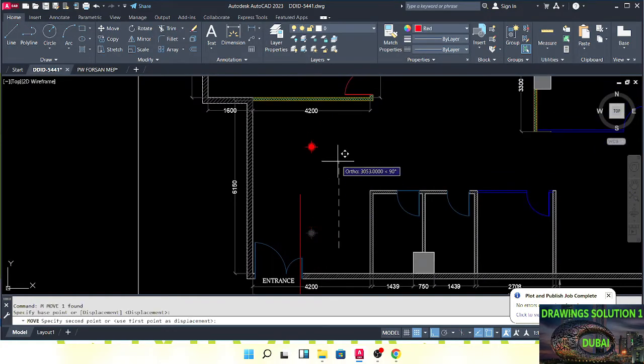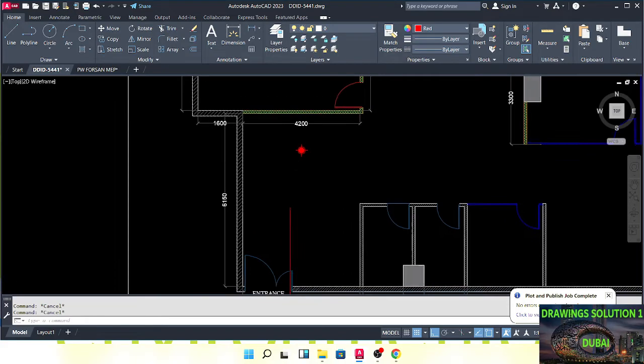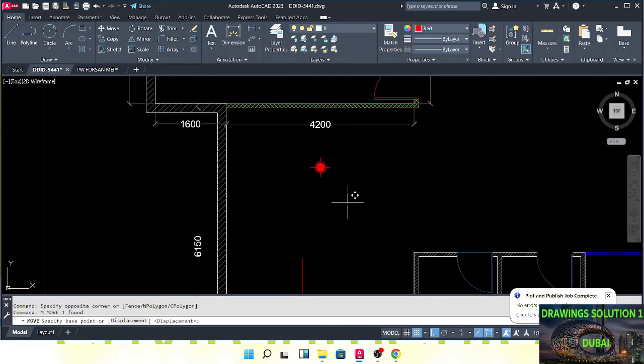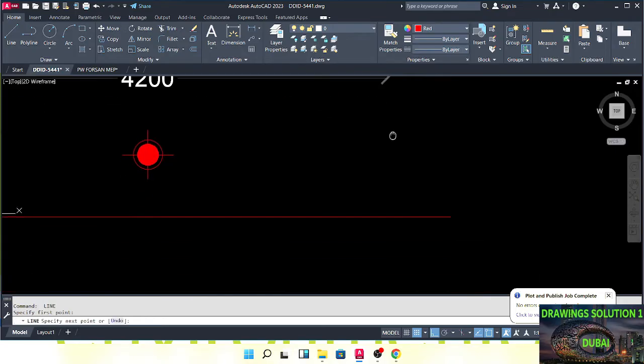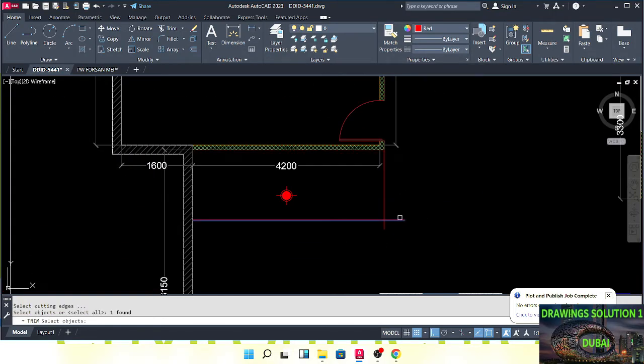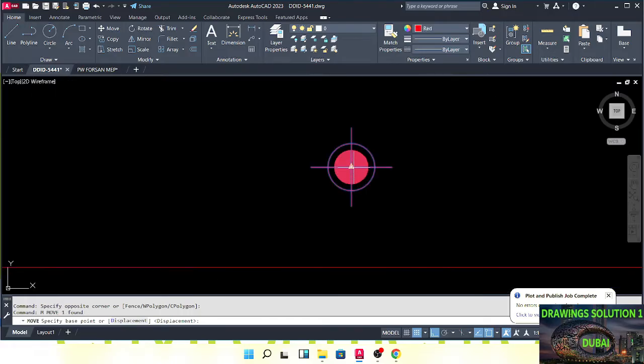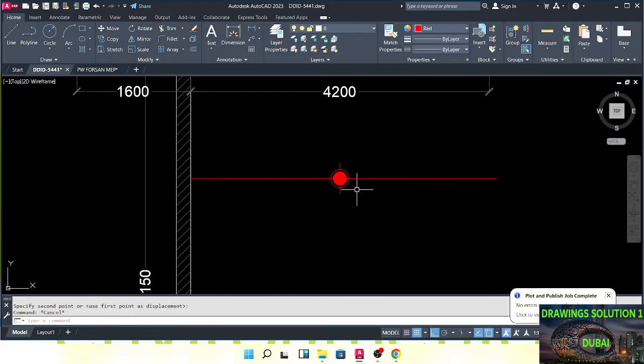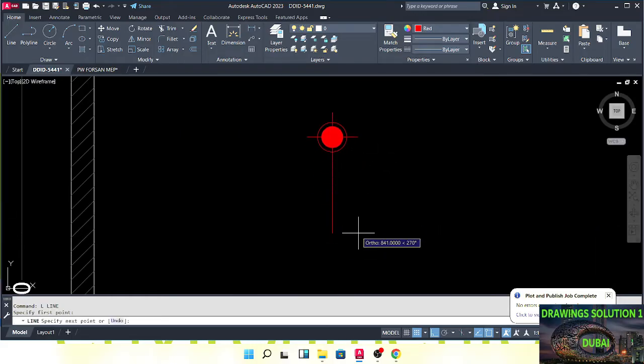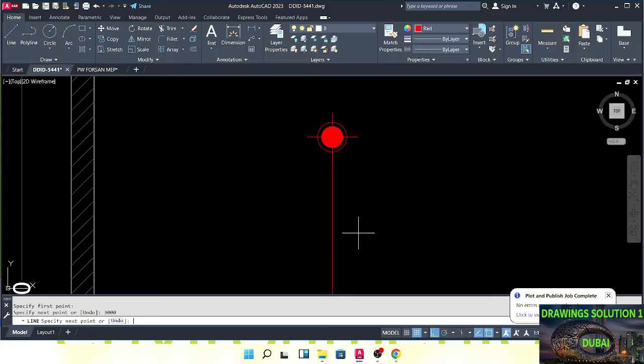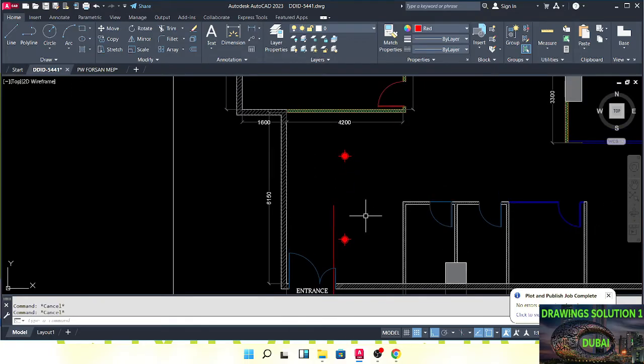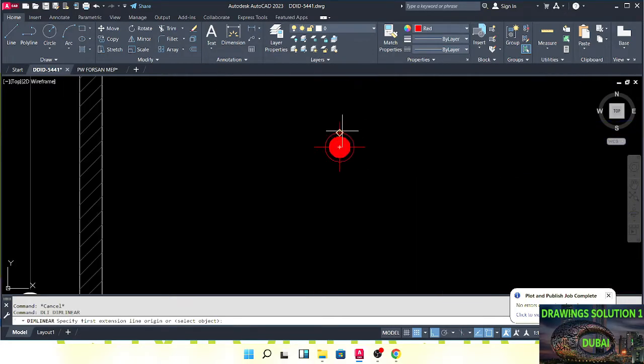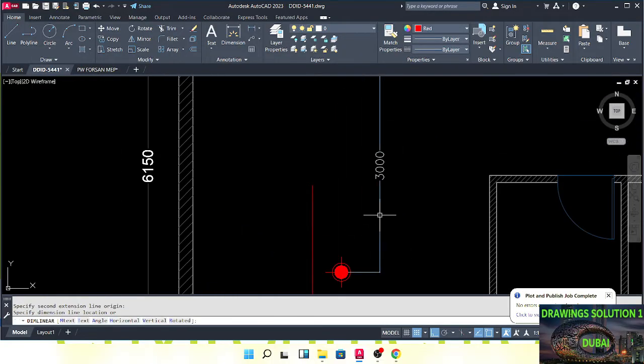From sprinkler to sprinkler we need 3 meters. If we have somewhere with less space we can make it 2.5 meters also, but the standard is 3 meters distance from the center of one sprinkler to the center of the next sprinkler. So here I will follow 3 meters from center to center.